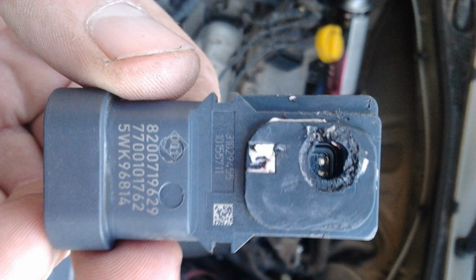After taking the gauge readings, the device should be disconnected, connecting a vacuum pump instead. Then it is necessary to create a vacuum at the level of 55 to 56 millimeters of mercury and stop pumping at this point. If this value does not change for 30 seconds after disconnecting the pump, then the sensor is in good order, otherwise the device will have to be replaced.